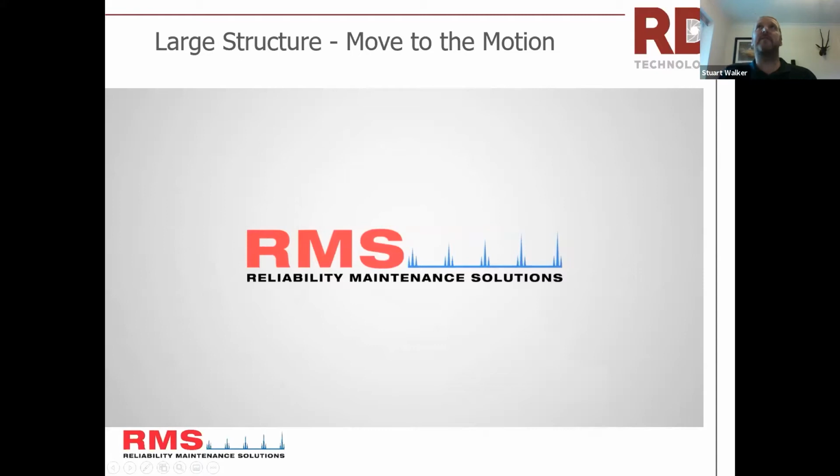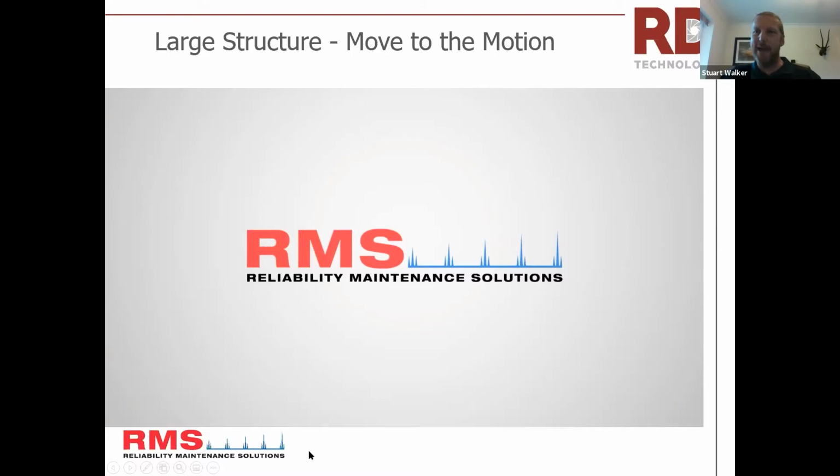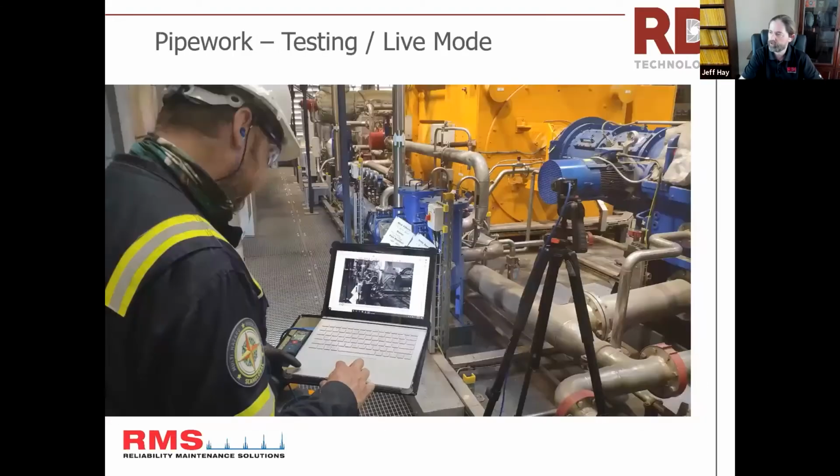If the forces there, say a 1 times, are an unbalance or misalignment, what you tend to see on the video is almost like the machine wanting to rip itself off the bed. You actually see the force and the vibration, and there won't be a looseness there, but you'll see the metal flexing and deforming, which is quite amazing. And I think towards the end, Jeff, haven't we got a good, amazing shot of something like that? We'll jump to the next one.